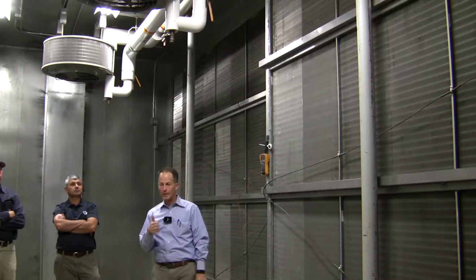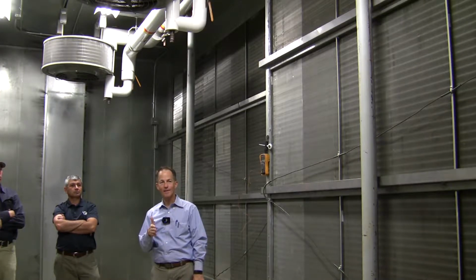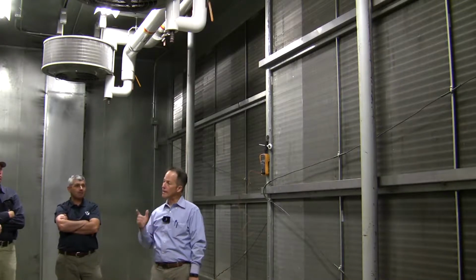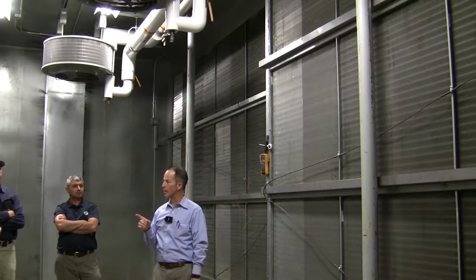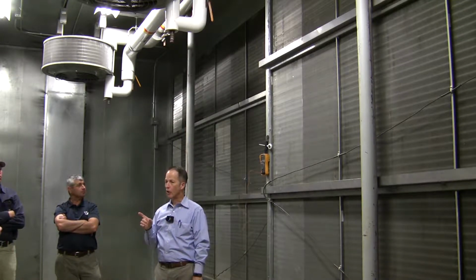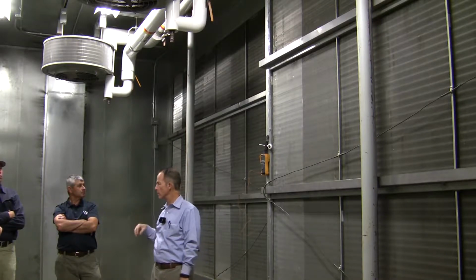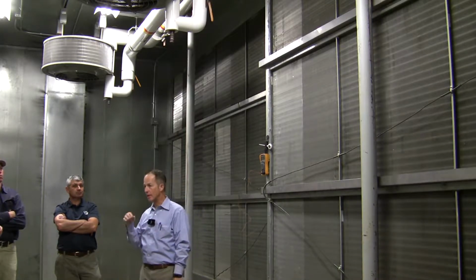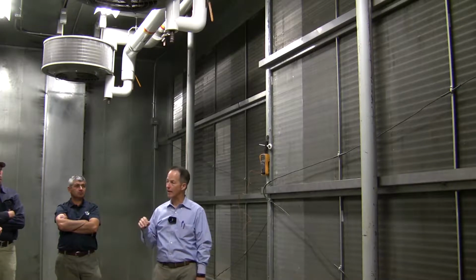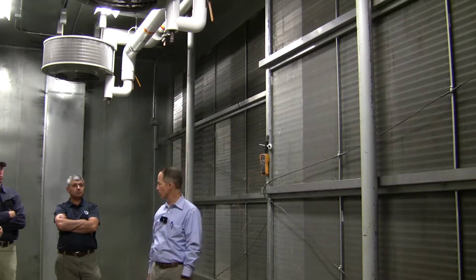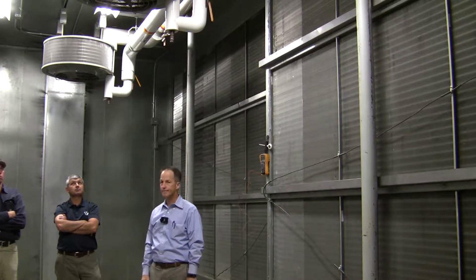This building's a pretty tight building, right, Brooke? Oh yeah. Okay, so tight building means we don't need as much outside air in the winter time, and it works in the case of this building. If you had a really leaky building where you needed a lot of outside air, this may not work very well.